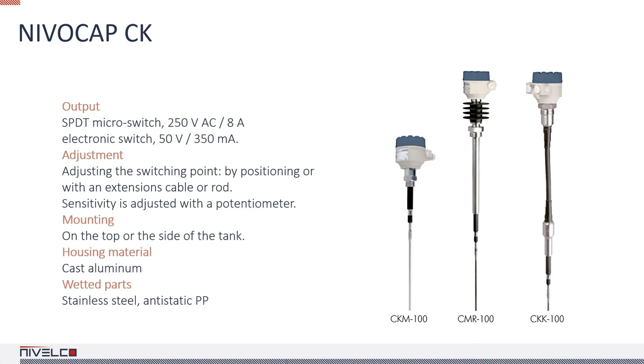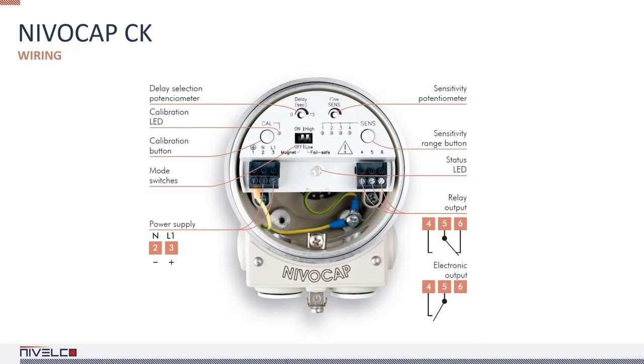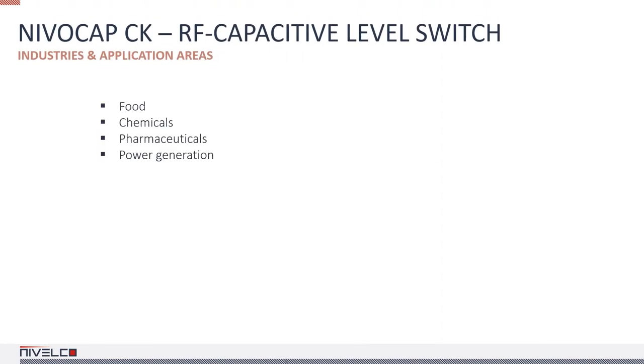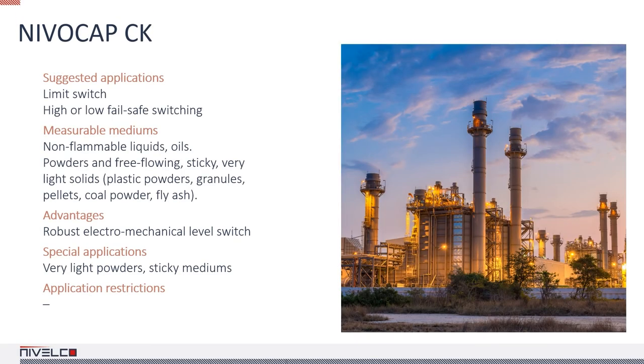The longest extension rod through probes is 3 meters, while extension cables are available up to 10 meters. The shortest insertion length is 12 inches, the highest process temperature is 430 degrees, and the highest ambient temperature is 95 degrees Fahrenheit. Only the lower metallic parts of the probe can come in contact with liquid mediums. The approximate sensitivity can be set in four ranges and fine-tuned with a potentiometer. The NIVOCAP CK100 is an excellent choice for viscous, sticky substances where vibrational and other contact measurement technologies are not applicable. It is often used in the ash and slag tanks of power plants, but is also effective in media where adhesion is unavoidable. It can be used for limit switching and high or low fail-safe switching with liquids, powders, free-flowing solids, and sticky materials.